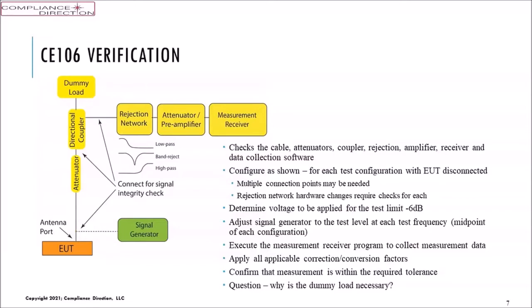So we have to use some caution when we do that. Just like everything else, we test to the limit, 6 dB below the limit, and adjust the generator to make sure it measures correctly. I get through another question here. Why is the dummy load necessary?